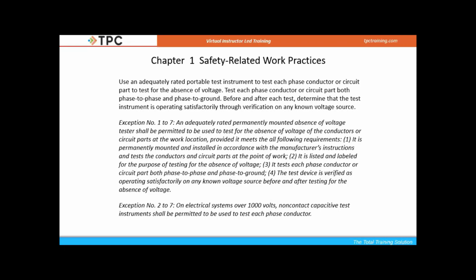Exception number two, we do all the time. If we are at medium voltage, so above 1,000 volts, all the way up to 15,000 volts, they are allowing us to use a non-contact tester. So I would have a hot stick in this case. I would have my non-contact tester mounted onto the end of my hot stick, and I would test that before I did phase to phase or phase to ground. I would make sure that my non-contact tester was working properly, and make sure I tested it after also.